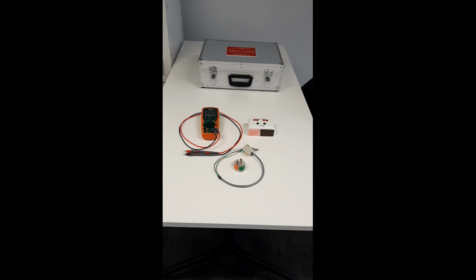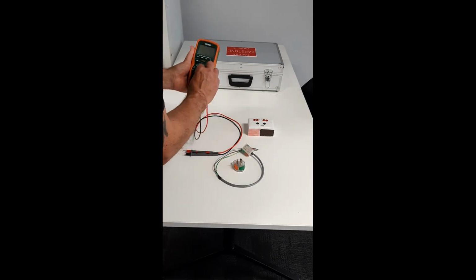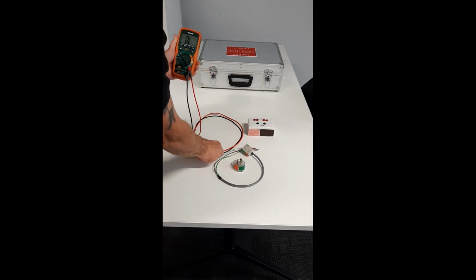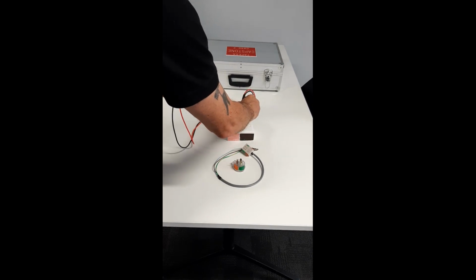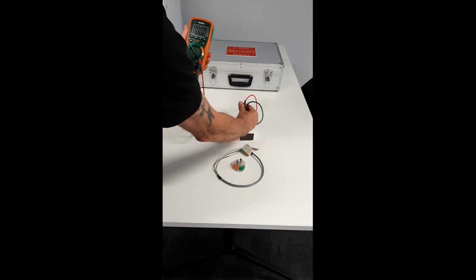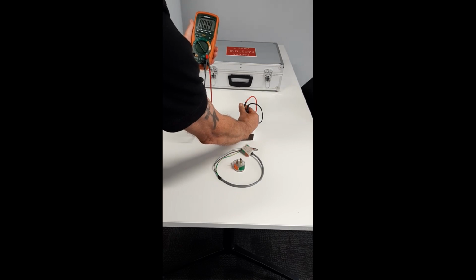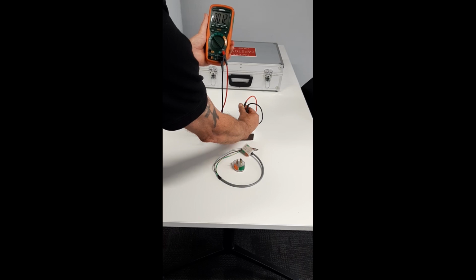Device setup. Prior to testing, inspect the probe tips and the leads and place them in the correct terminals of the meter. Select the ohm scale. Measure a low value of resistance, for example, 1 ohm, to check the accuracy of the meter. I'm recording approximately 1.1 to 1.2 ohms.